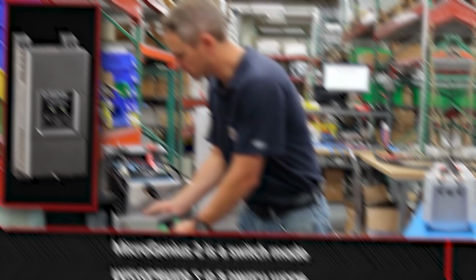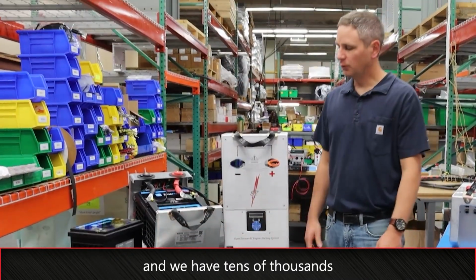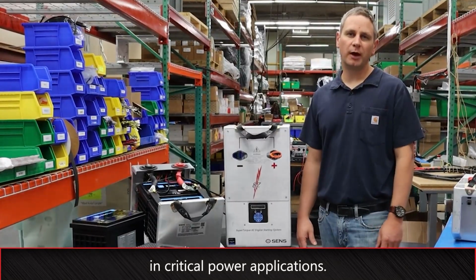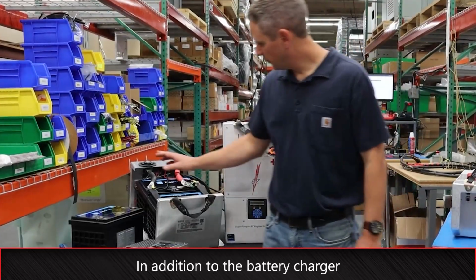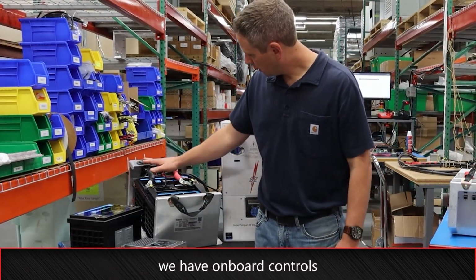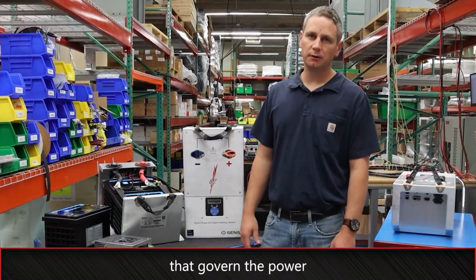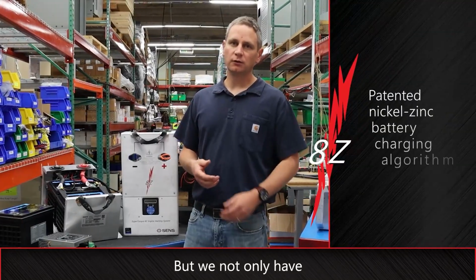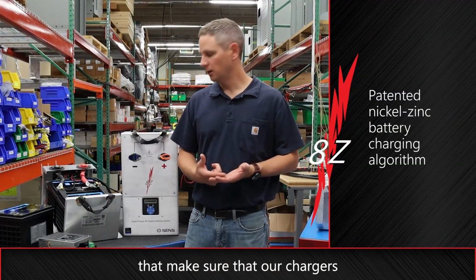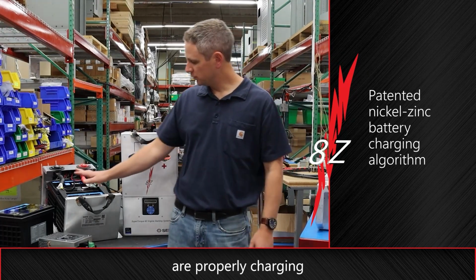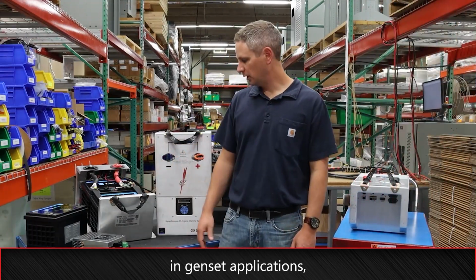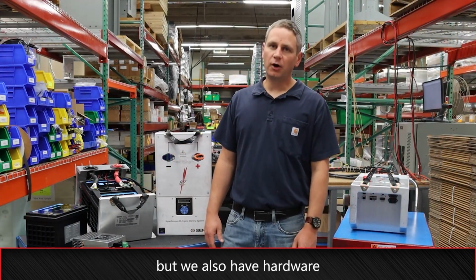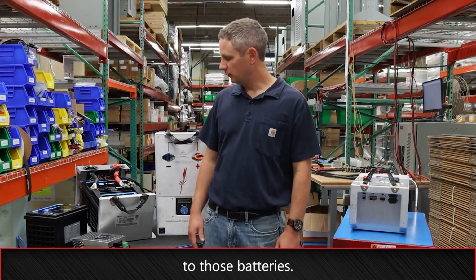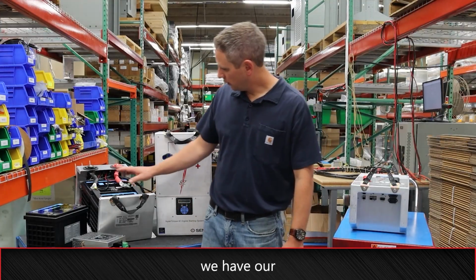We also have on board a SENS MicroGenius 2 battery charger. The MicroGenius 2 is a switch mode battery charger, and we have tens of thousands of those in the field today in critical power applications. In addition to the battery charger and the batteries, we have onboard controls that govern the power from the charger to the batteries. So we not only have sophisticated charging algorithms that make sure that our chargers are properly charging to full capacity in genset applications, the nickel zinc chemistry, but we also have hardware that limits and controls the current to those batteries. In addition, we have our communication set and our user interface.